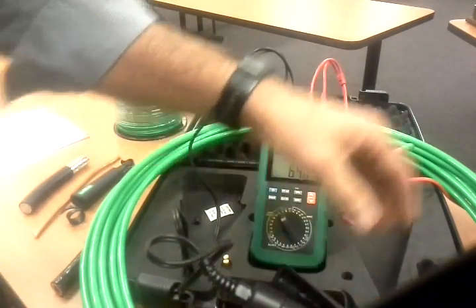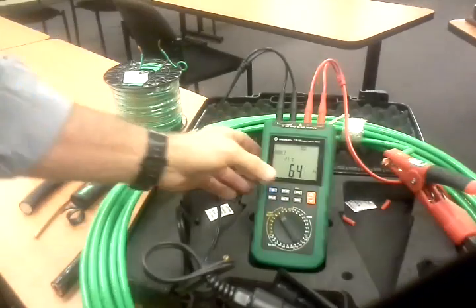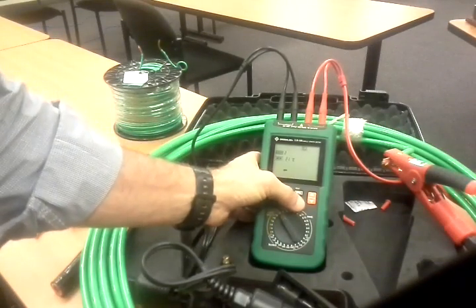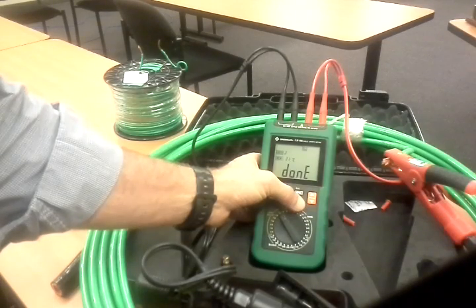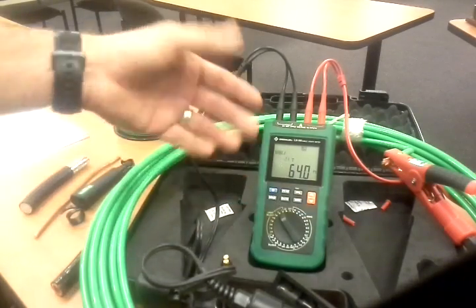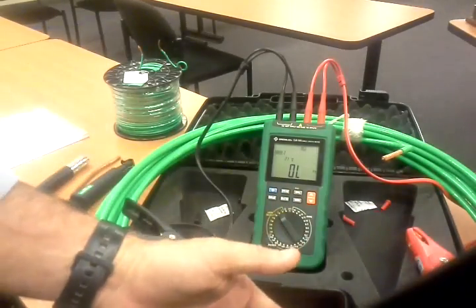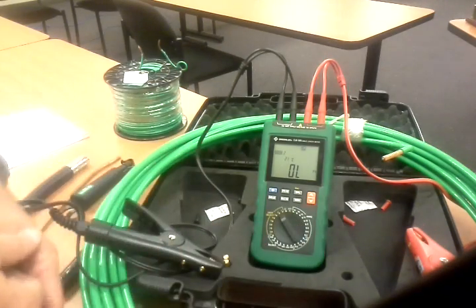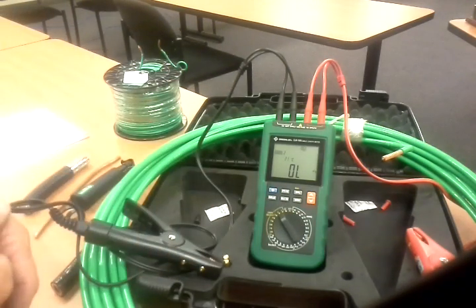We'll hook up our leads. We'll press memory. The 4 dashes come across. Done. That's now set. We can pull these leads back off. And again, when we come back to measure this, we're now set for this particular size cable. If it was a special size cable, you have 8 presets that you can set.